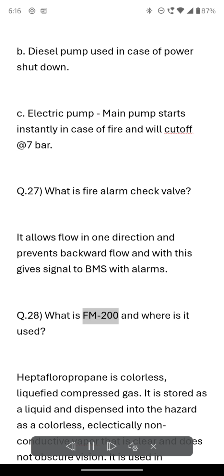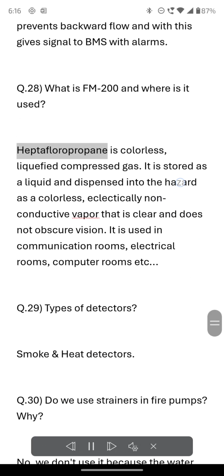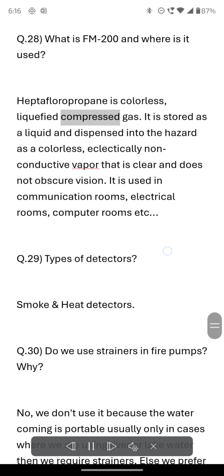Q.28 What is FM200 and where is it used? Heptafluoropropane is a colorless, liquefied compressed gas. It is stored as a liquid and dispensed into the hazard as a colorless, electrically non-conductive vapor that is clear and does not obscure vision. It is used in communication rooms, electrical rooms, computer rooms, etc. Q.29 Types of detectors. Smoke and heat detectors.